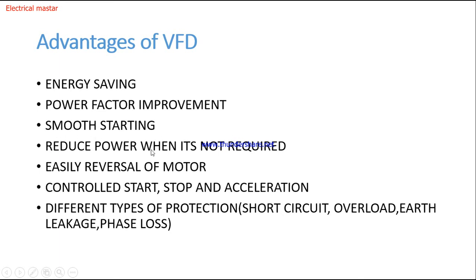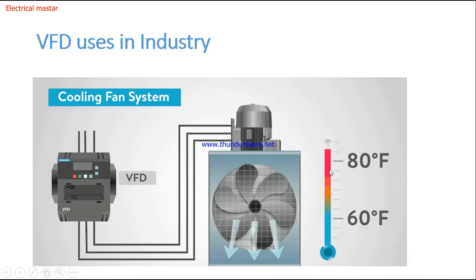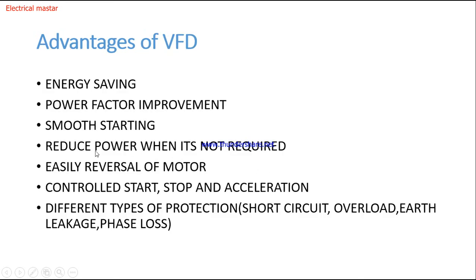Fourth, reduced power when not required: as shown in the cooling fan example, when temperature is at 60°, VFD controls the speed to 30%, reducing motor power consumption by 70%. Fifth, easy motor reversal: just give a command to change the rotation without changing cable connections. Sixth, controlled start, stop, and acceleration. Additionally, VFD provides built-in protection including short circuit, overload, earth leakage, and phase loss protection.